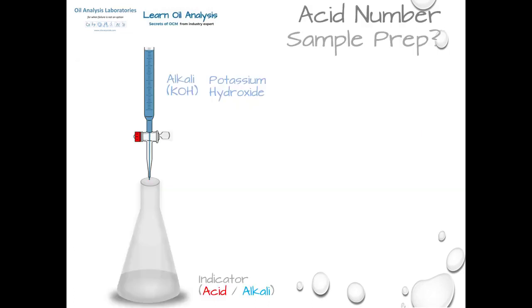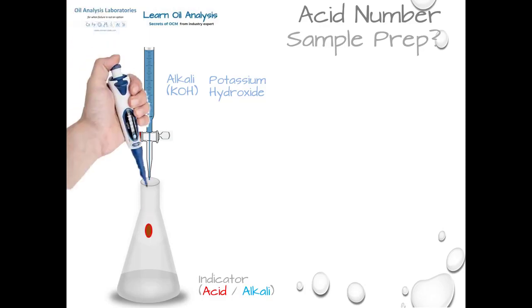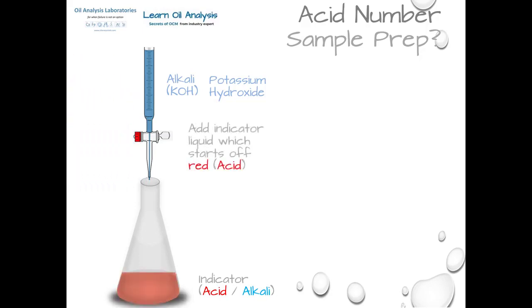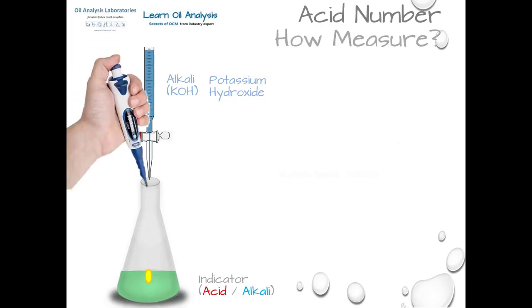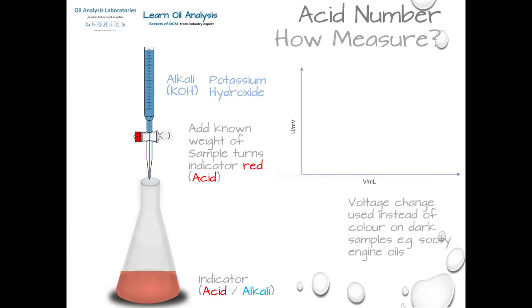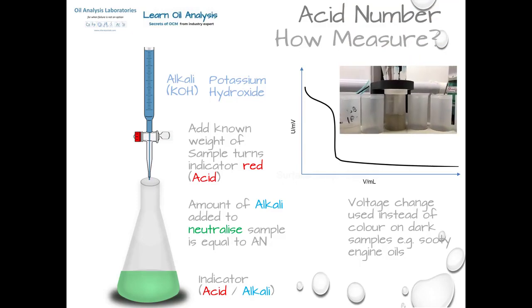An acid number is measured in milligrams of KOH per gram — that is, how much alkali is needed to neutralize the acid. In colorimetric titrations, a colour change is used similar to litmus paper. The indicator is red/green: we titrate a small amount of KOH to bring the indicator to the neutral green stage, add a known weight of the acidic sample which turns it red, then add additional alkali until it returns to green. We now know how much alkali was needed to neutralize the known weight, giving us the acid number in milligrams of KOH per gram.